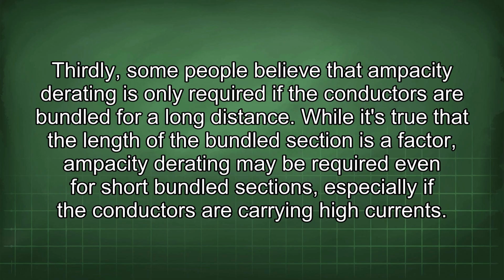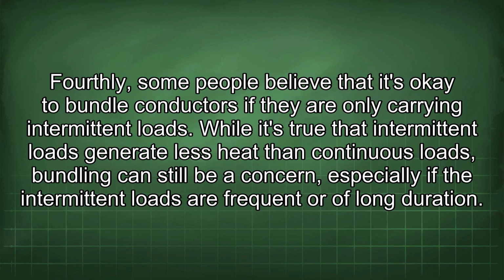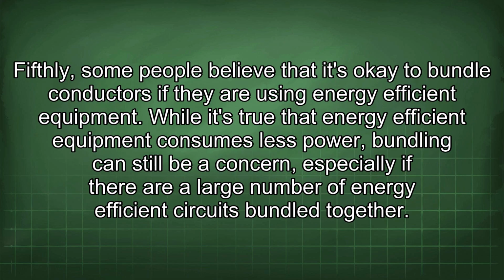Thirdly, some people believe that ampacity derating is only required if the conductors are bundled for a long distance. While it's true that the length of the bundled section is a factor, ampacity derating may be required even for short bundled sections, especially if the conductors are carrying high currents. Fourthly, some people believe that it's okay to bundle conductors if they are only carrying intermittent loads. While it's true that intermittent loads generate less heat than continuous loads, bundling can still be a concern, especially if the intermittent loads are frequent or of long duration. Fifthly, some people believe that it's okay to bundle conductors if they are using energy-efficient equipment.